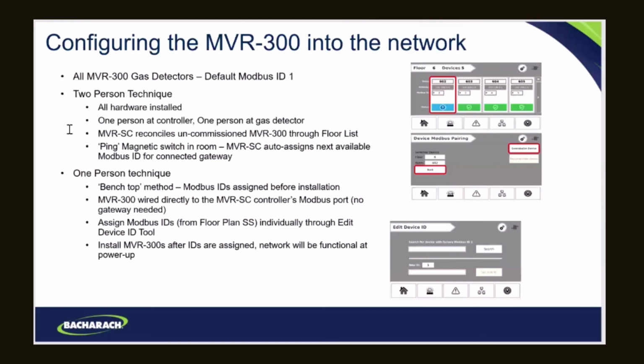And we call this the two-person technique. One person is typically at the controller. In your instance, that's going to be in your mechanical room, wherever that is. And the other person will be the roamer, or the person going around to each one of the gas detectors to help with the commissioning. So as the MVR-SC walks through the floor list, it will see these individual gas detectors that still have to be commissioned. So what's going to happen is the guy at the controller is going to click on this.